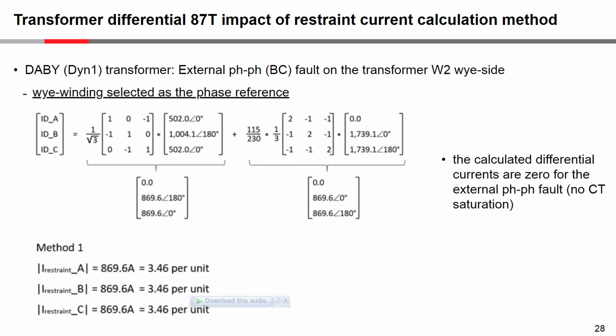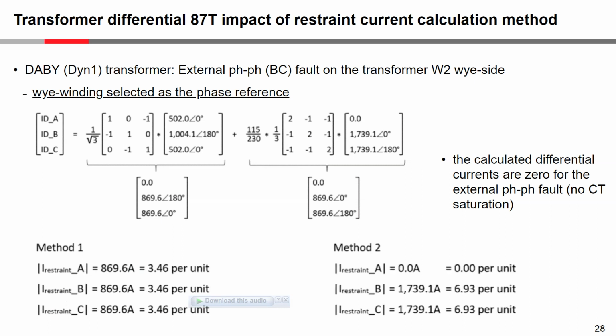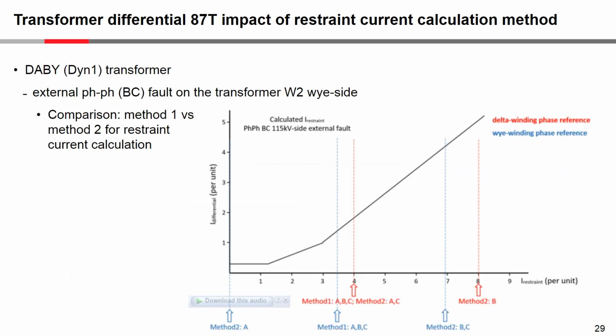And right, so now let's look at the calculation of the restraint current. If you're using method 1, you would look at those 6 currents, and theoretically 4 of them are the same, but that would be the chosen restraint value, and it would be applied to phases A, B, and C. If we look at method 2, for phase A the theoretical calculation would give 0. And for phases B and C it would be the 869 plus 869, and so you get that value of 1739. So let's see how that actually looks on a characteristic.